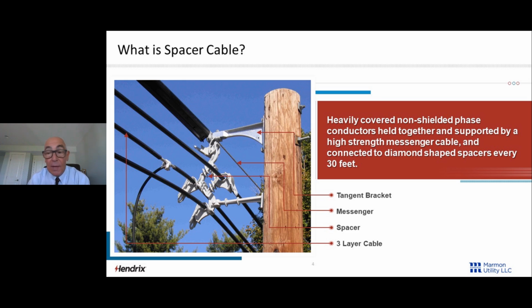We've got spacers, which are basically hangers. Putting those 3 conductors on the spacer is like putting your shirt on a hanger and hanging it in the closet. Those phase conductors are under no tension whatsoever. They're just sitting in the spacers and hung on the messenger.